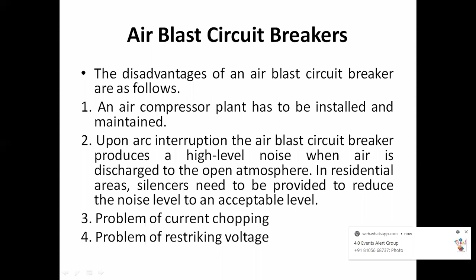Okay, so these two disadvantages, the problem of current chopping and the problem of restriking voltage, are related to the technical aspect, so you can reduce these values. But on the other hand, the other two disadvantages, that we have to install the air compressor and the noise pollution, you cannot reduce. So you can reduce the current chopping value and improve the restriking voltage, and in that way you can improve the circuit breaker. But again, certain disadvantages of the air blast circuit breaker remain.